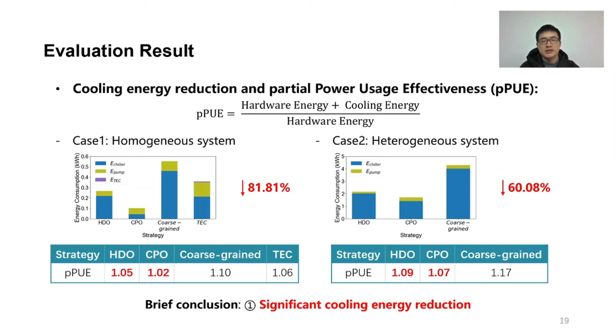We investigate two cases in the evaluation, including the homogeneous system with only CPU and the heterogeneous system with CPU, GPU, and DRAM. As we can see, our solution can lower the cooling energy by up to 81.81% and improve the partial PUE to as low as 1.02, which means if the hardware consumes 1 unit of energy, our solution only needs another 2% of energy for cooling.